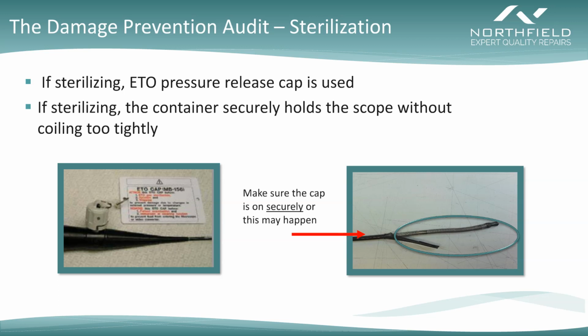And the reason for that is because the first thing your sterilizer does in the sterilization process is it sucks all the air out of that chamber, which creates this incredible vacuum. Now, if there is air trapped inside that scope, that air will violently want to get out. And that's what you see on the right-hand side of the screen there. This was a scope that was put into a sterilization chamber without the cap in place. And that air, if it can't find a way out, it will make its own way out. And that's what you see when you see that blown tip.